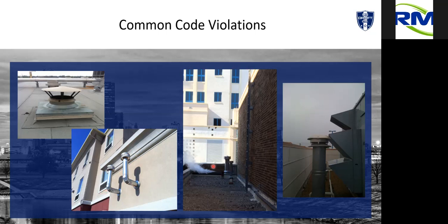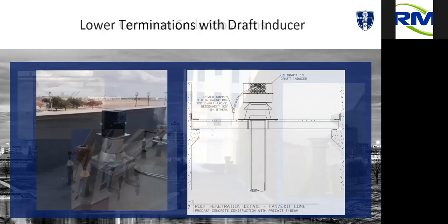So they cleared this little parapet wall. They forgot about this 12-foot wall on this side, so they could have fixed that. Now this one I just throw up here to shake my head at. That is an exhaust pipe dumping into a makeup air louver. I can't fix that. I would love to know who the contractor was so that I can have their license stripped. But yeah, that's not going to work. That's just one of those you just have to shake your head at.